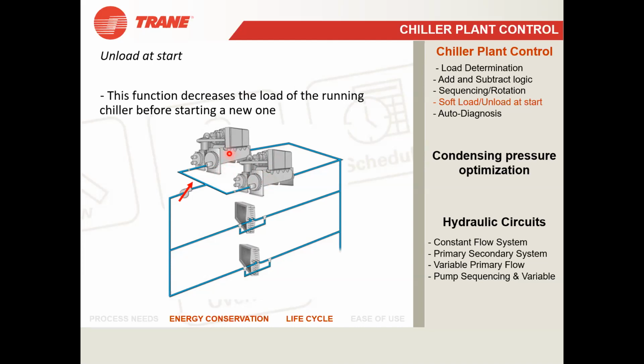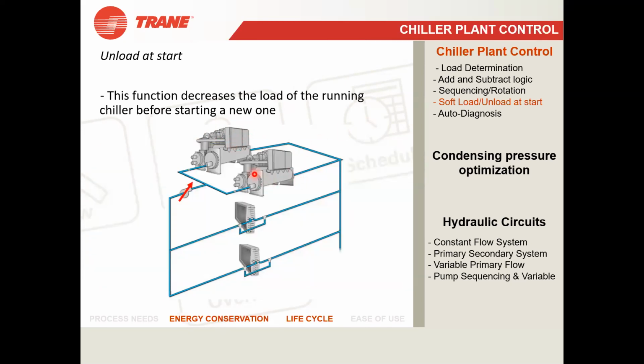When the second chiller switches on, all the accessories behind it, like all the pumps, will be switching on. Just imagine your first chiller was running at 100% and you are now switching on your second chiller and all the accessories. Then what will the electricity bill be? And if you reduce this chiller to its minimum load, that is 15 to 20%, whatever minimum load it can carry, you are reducing this for a fraction of a second. Actually, this is like milliseconds, in fact.